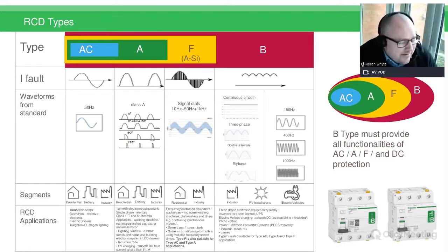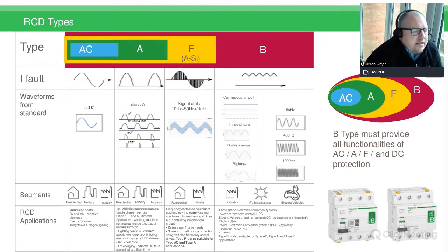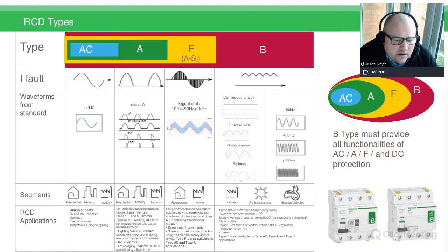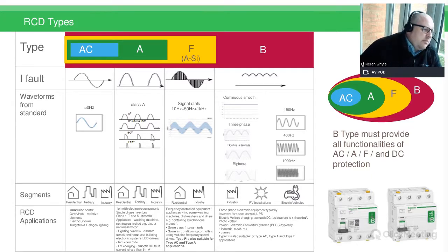When RCDs were first brought to the market, the majority of loads that would sit on them were resistive type, just an element. But as technologies evolved, we're seeing more and more DC effects pushed back onto the AC circuit, and these DC effects can cause a blinding effect on the RCD, so it won't operate when it meets its milliamp threshold. So originally we had the AC type, in simple terms, more for resistive loads.